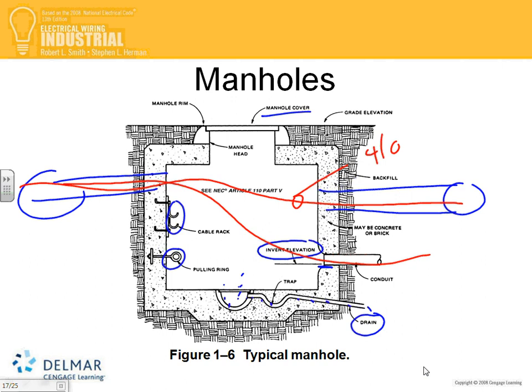There's also a requirement, guys, I believe this cover has to be 100 pounds or more, or you have to have a key to open it. If you have a transformer inside the manhole, good luck. It moves you completely to a whole different set of ventilation issues with transformers. If you have medium voltage, you have to go look at the medium voltage requirements.